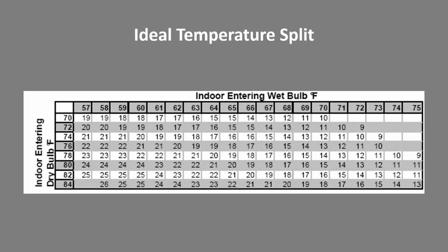So here in the Northwest, we often talk about having an ideal temperature split of 20 degrees. And sure enough, if we have a wet bulb of 62 degrees, which is common, and an indoor entering dry bulb of 76 degrees, 20 degrees is a pretty good target. But some days we get out there and it's kind of muggy, and it's actually a 68 degree entering wet bulb, and we have a 72 entering dry bulb. Our sensible split would only be 13 degrees. What's happening here is you're releasing quite a bit of energy when you turn all that water vapor back into liquid, and that lowers your sensible capacity.